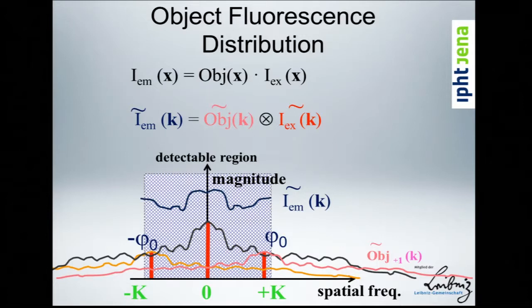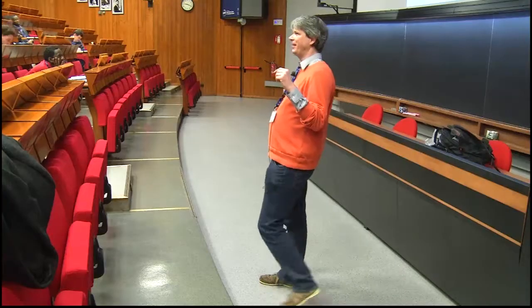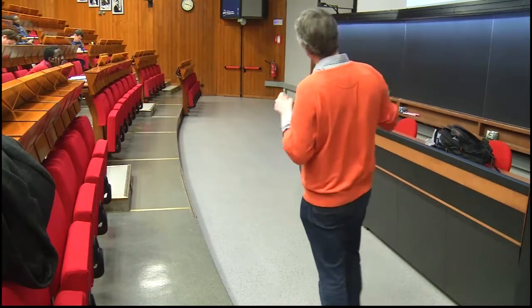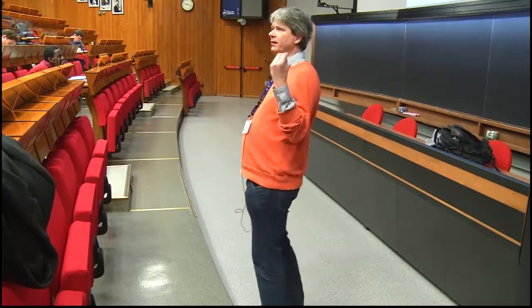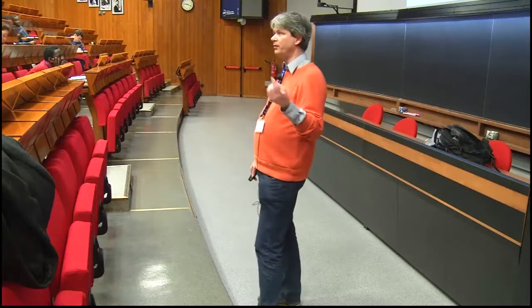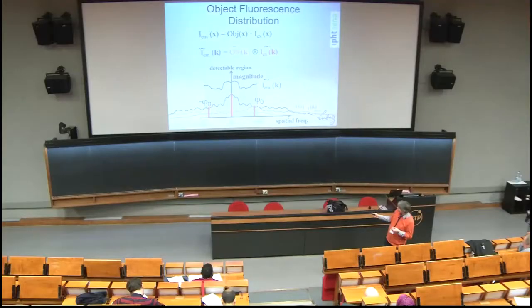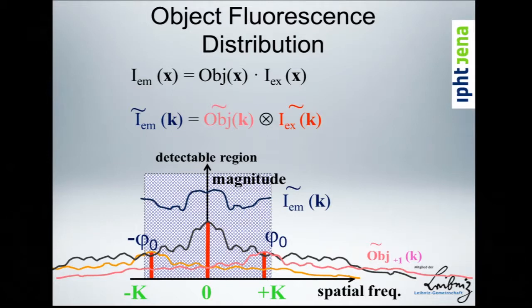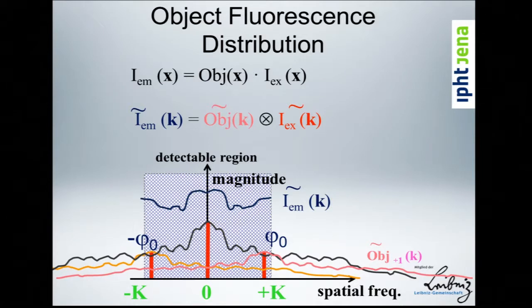We have these three shifted object components. The Abbe limit constrains what spatial frequency range we can obtain. If we were able to unmix that mess — from our measurements get back our object components — then we can shift them where they should belong, stitch them together, and get a high-quality high-resolution image. That's the whole point of structured illumination microscopy.